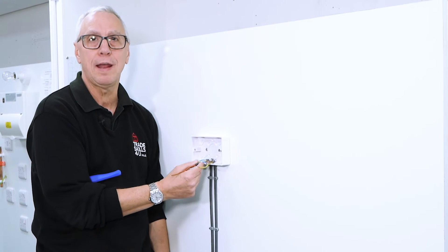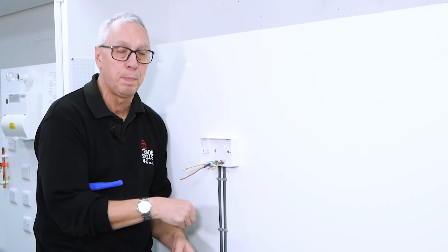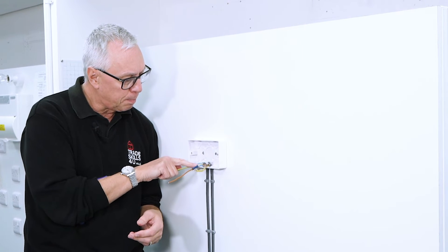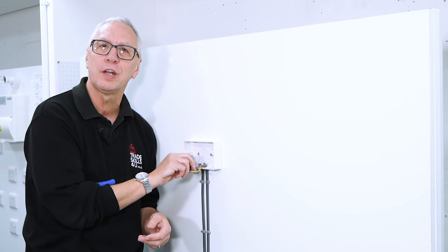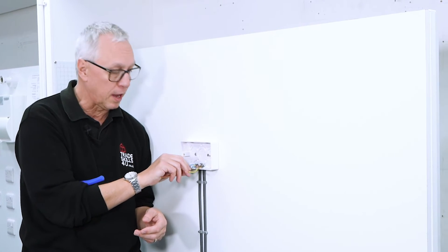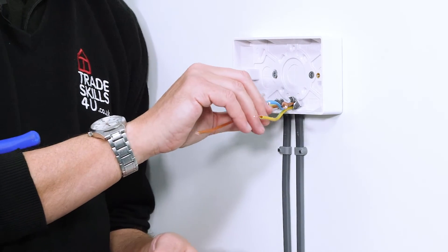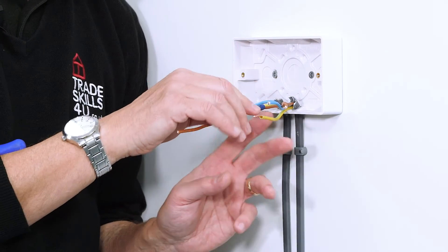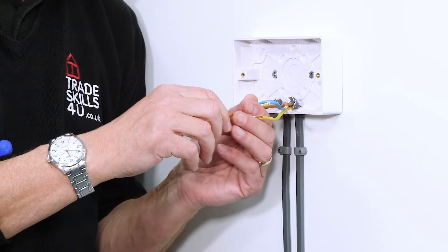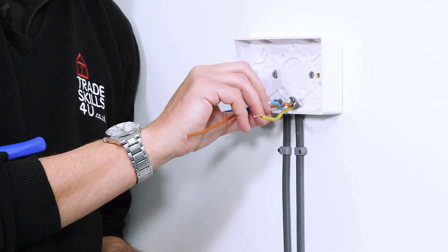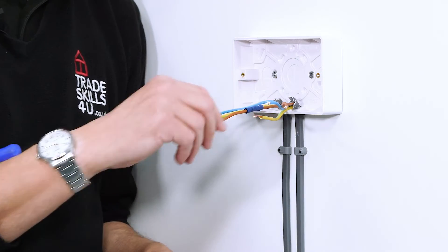So these inline crimps can be used to repair cables that have, say, been broken in a wall. But the outer insulation, the outer sheath, should I say, that is on a twin and earth cable has to be reinstated if that's the case. So these can be used as permanent connectors where there's been some damage. But you must make sure that the cable is doubly insulated when you've finished.